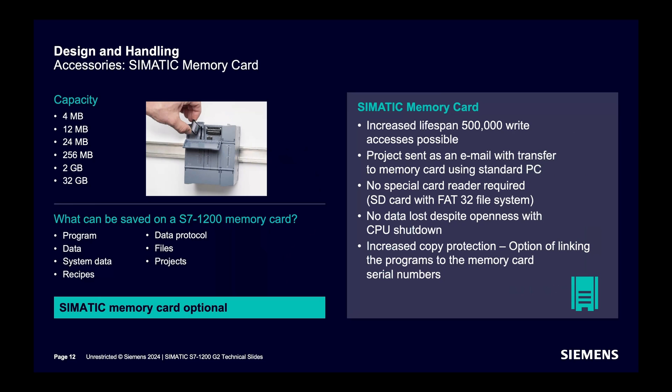The SIMATIC memory card for S7-1200 is available in capacities from 4 megabytes to 32 gigabytes. Programs, data, system data, recipes, data protocols, files, and projects can be saved on the memory card. The lifespan of the memory card is increased to 500,000 write accesses. No special memory card reader is required. Increased copy protection by linking the memory card with the CPU serial number is supported. However, the memory card is not mandatory in an S7-1200 CPU.